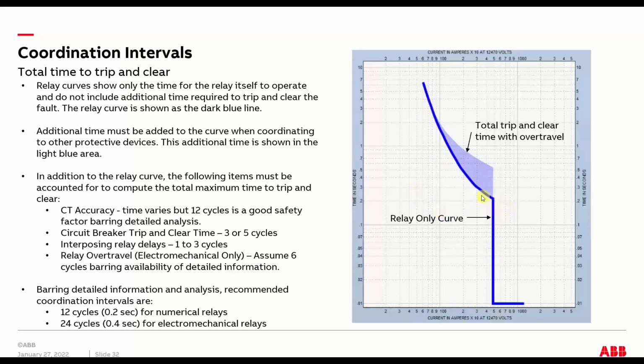So this blue line is the relay, and then I drew in this light blue hatched area would be the additional time that you need to be wary of to allow for the breaker to pick up, trip, and clear. And that ranges, and this also includes some of the accuracy of the CT, plus artifacts of the relay itself, like electromechanicals had an over travel where they sort of spin down.